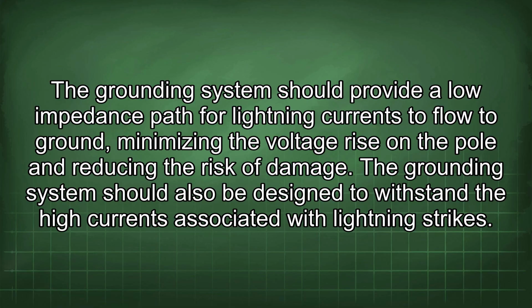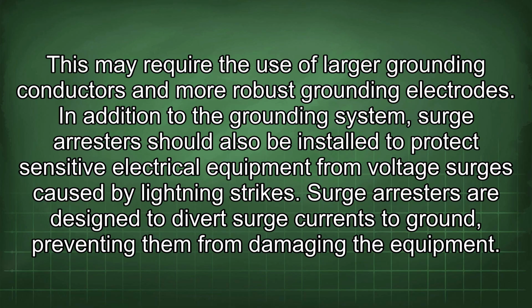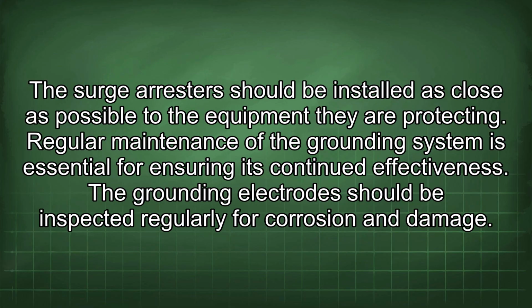The grounding system should also be designed to withstand the high currents associated with lightning strikes. This may require the use of larger grounding conductors and more robust grounding electrodes. In addition to the grounding system, surge arresters should also be installed to protect sensitive electrical equipment from voltage surges caused by lightning strikes. Surge arresters are designed to divert surge currents to ground, preventing them from damaging the equipment. The surge arresters should be installed as close as possible to the equipment they are protecting.